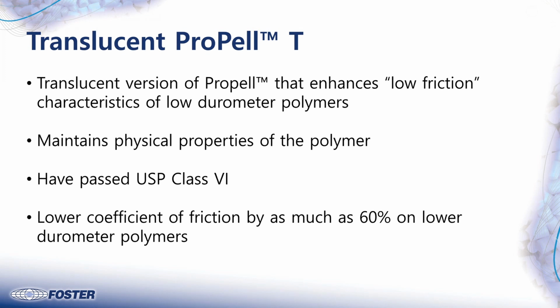Again, USP Class 6, and we're going to see from some of the data, you can lower the coefficient of friction of a very sticky polymer, which are the low durometer PEBAs, low durometer polyurethanes, Pellethane trade name, quite significantly. You'll see that even some of the stiffer polymers like a nylon 11, nylon 12, which is reasonably lubricious, you can improve the lubricity of that. Adding some of these lubricants can also aid in the extrusion process and help out with manufacturability as well.